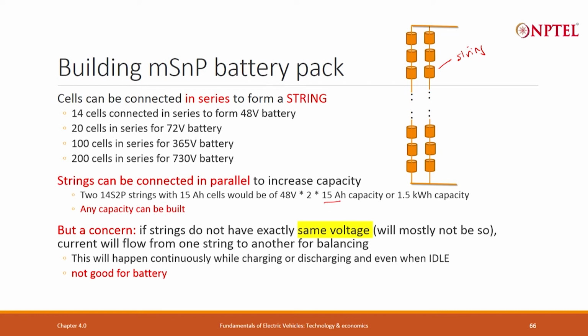But there is a concern. I put 14 of them in series. Let's say cells are at slightly different voltage at any time during charging or discharging. Suppose the voltage of one string works out to 51 volts, and for the other it works out to 49.5 volts. What will happen? The string voltages of the two strings are different, and you connect them in parallel. Immediately a current will start flowing, because the voltage has to be the same.